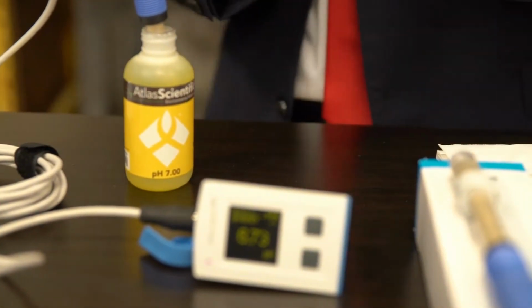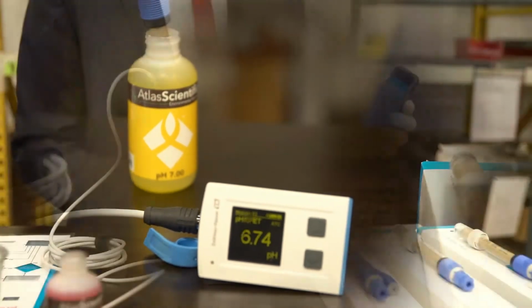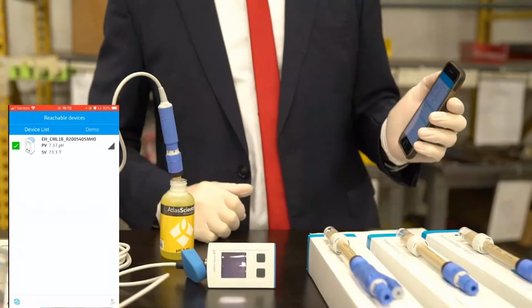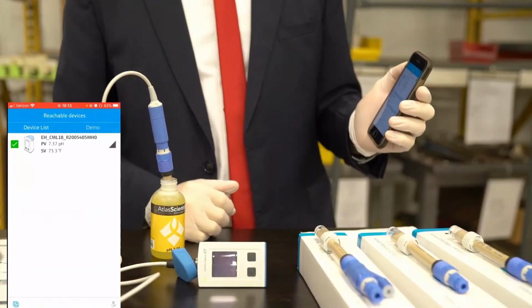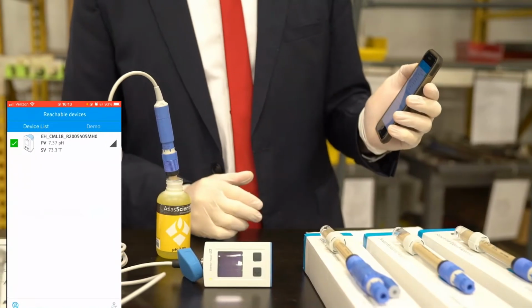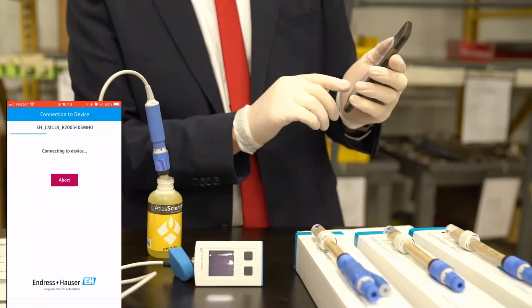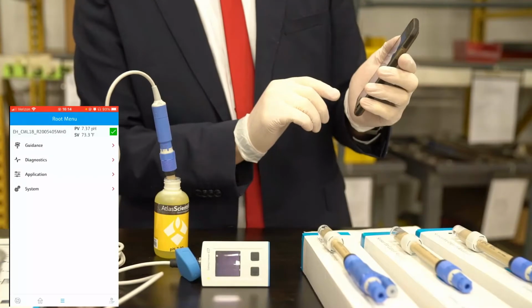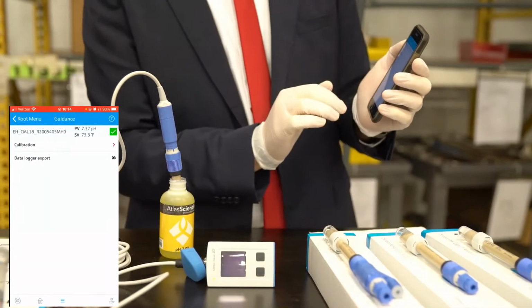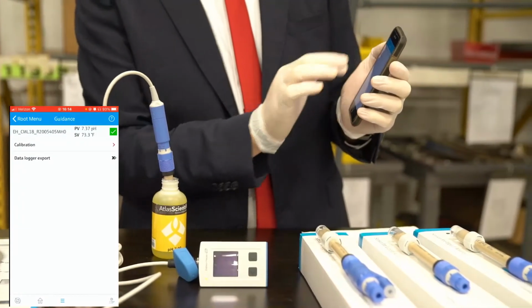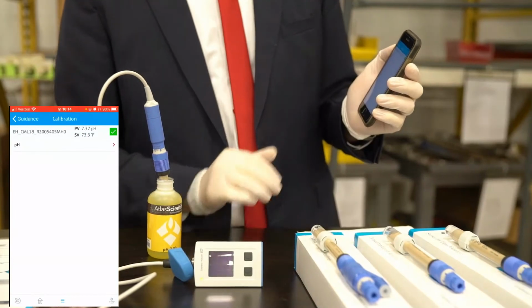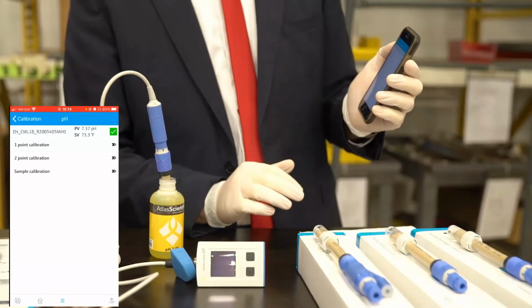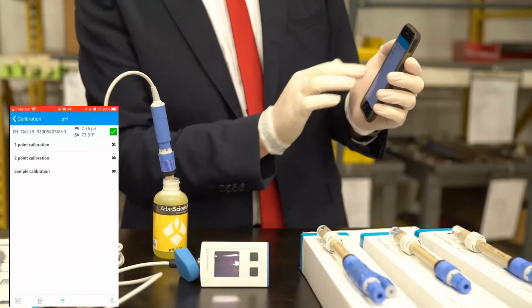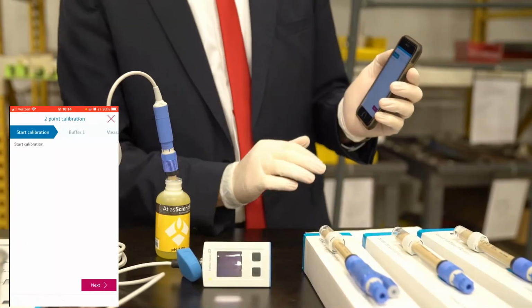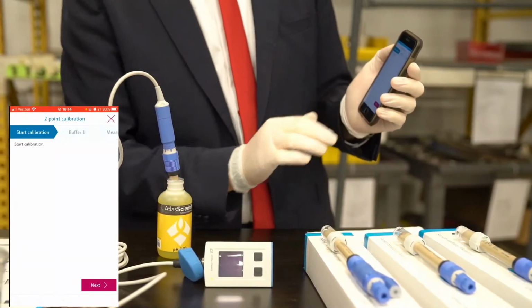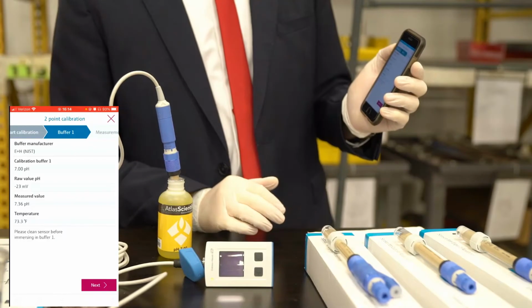Let me walk you through the steps. Once we are connected to the mobile transmitter, we hit the root menu, guidance, and we go to calibration. We choose pH, 2-point calibration, and we start the calibration. So it's a 2-point calibration.